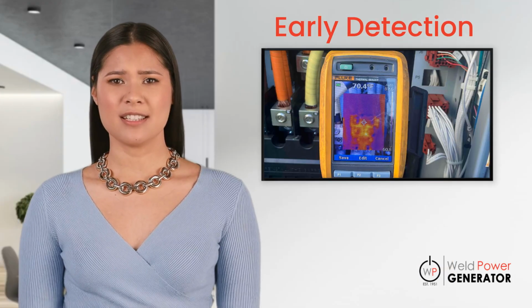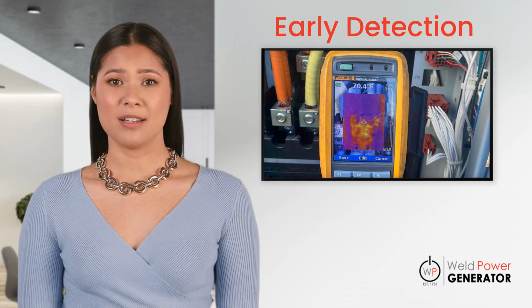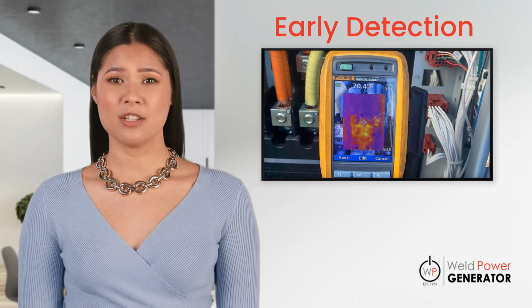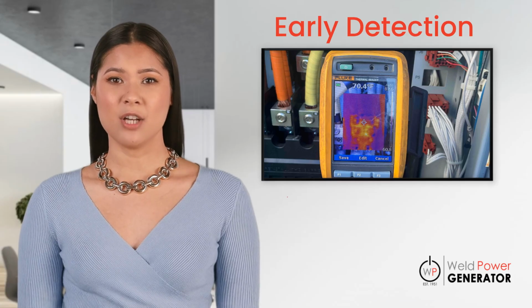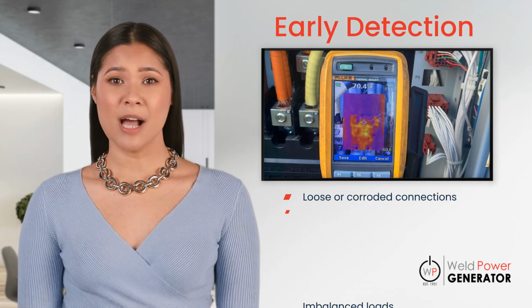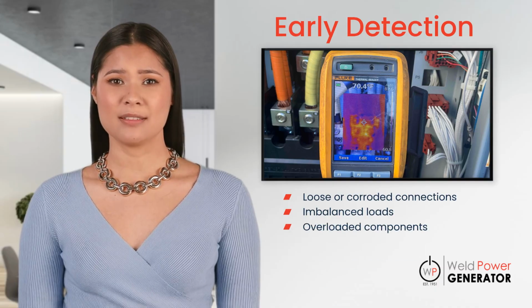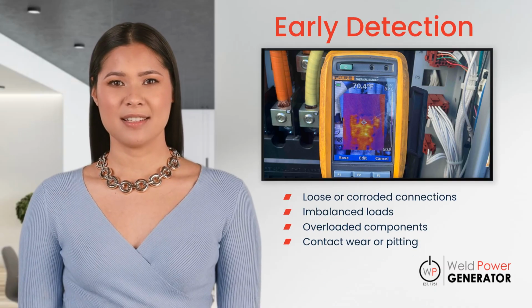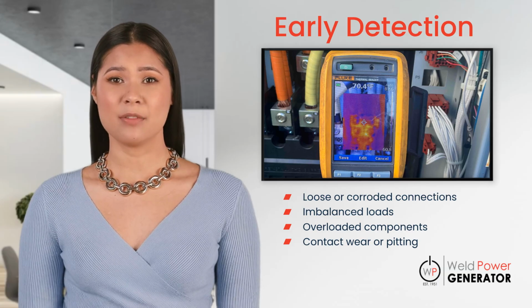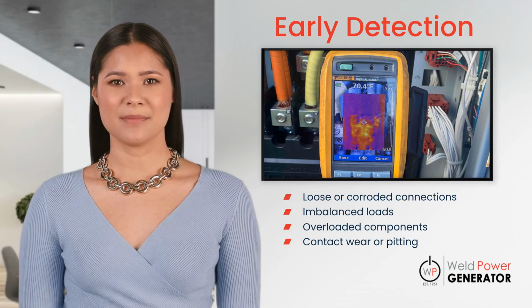Automatic transfer switches consist of electrical connections, contacts, relays, and internal wiring, all of which can degrade over time. A failing connection or overloaded circuit might not be visible during routine visual inspections, but thermal imaging detects abnormal heat patterns, pinpointing hotspots caused by loose or corroded connections, imbalanced loads, overloaded components, contact wear, or pitting. Identifying these anomalies early can prevent outages and unplanned downtime.